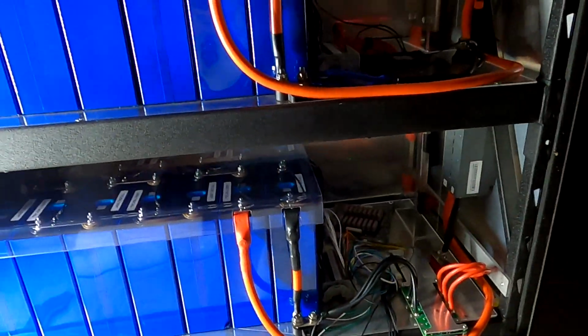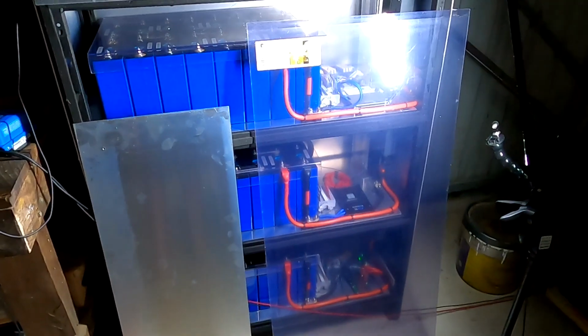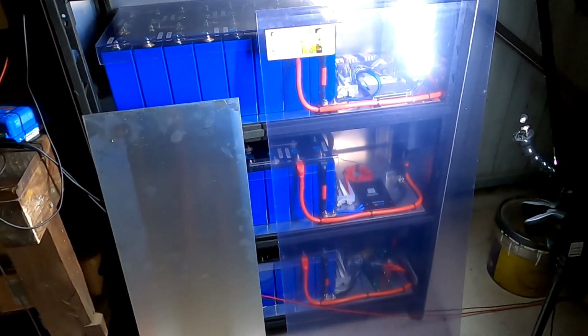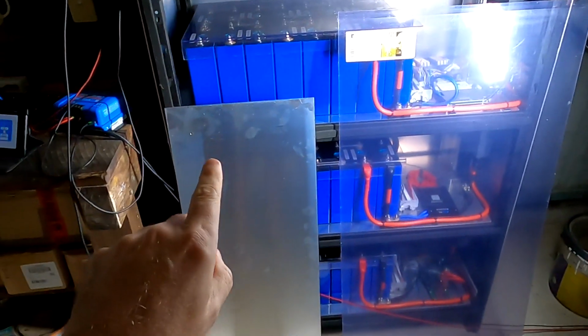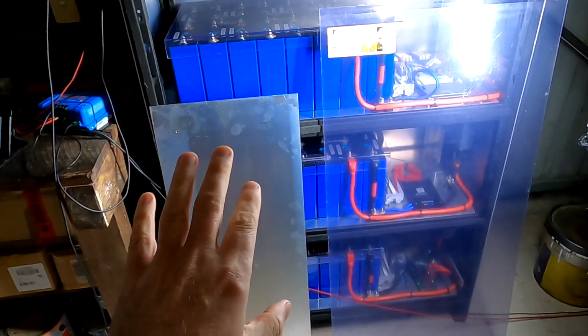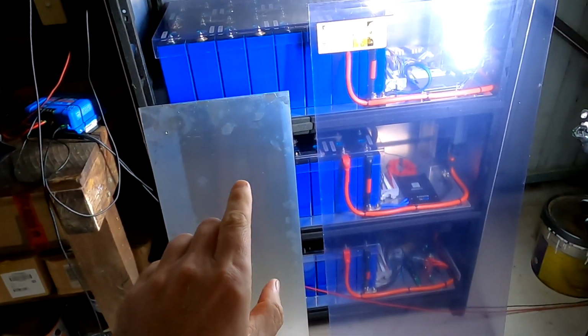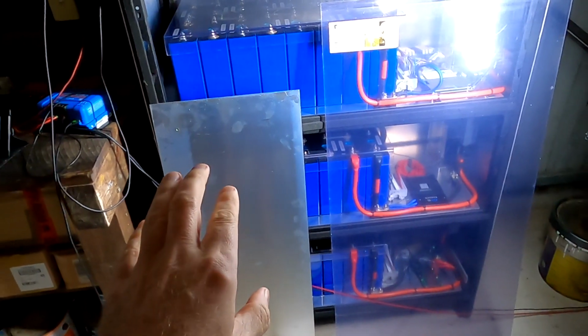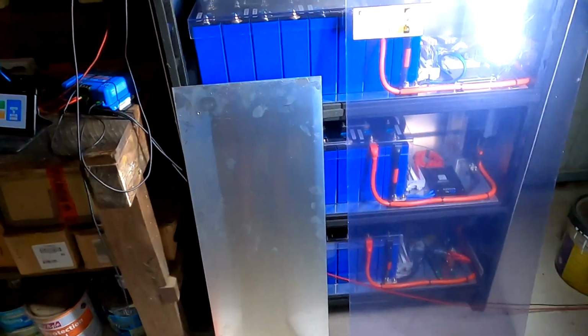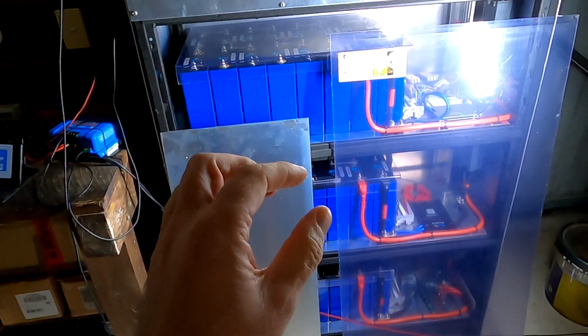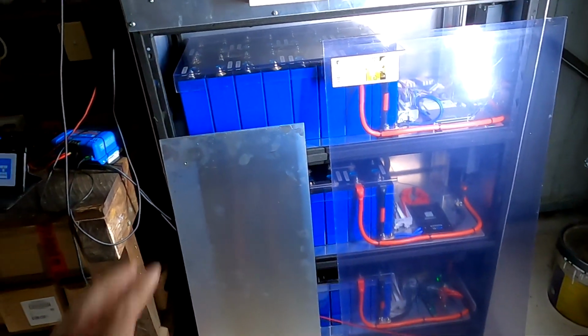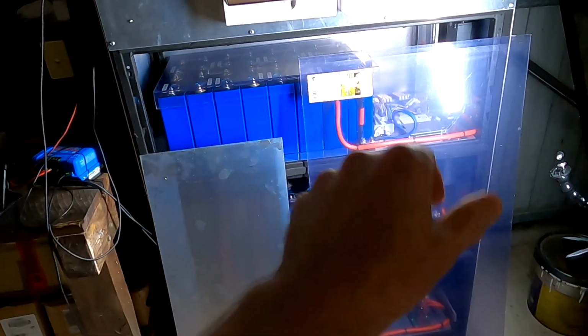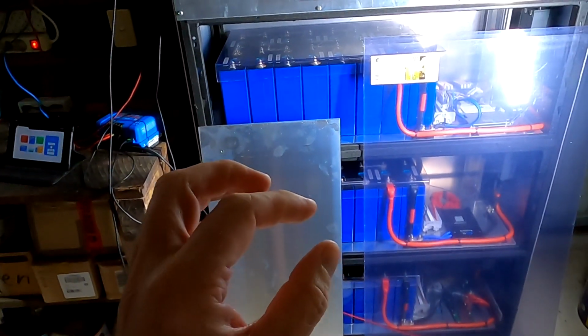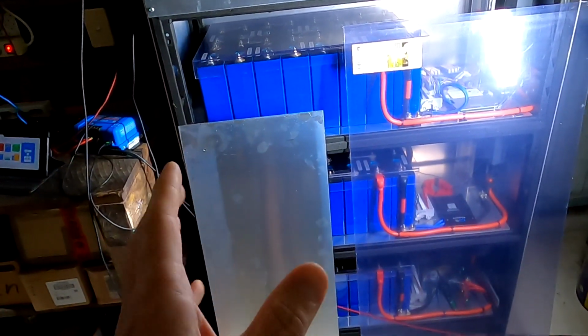All done. Yeah, guys, so now we have to make the decision if we want to cover these shelves with the aluminium plate, which would be, as per the regulations, non-combustible material, and you have to use screws. So it actually says you have to use a tool to remove the cover - it cannot be just a hinge and a latch or something, it needs to be some sort of screws or a lock or something like this.